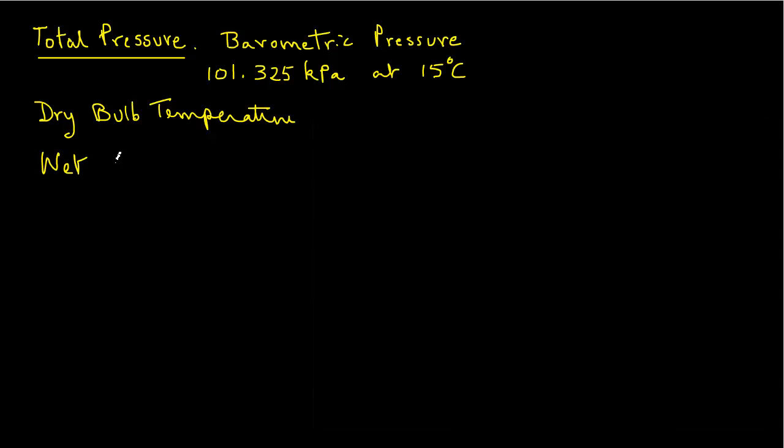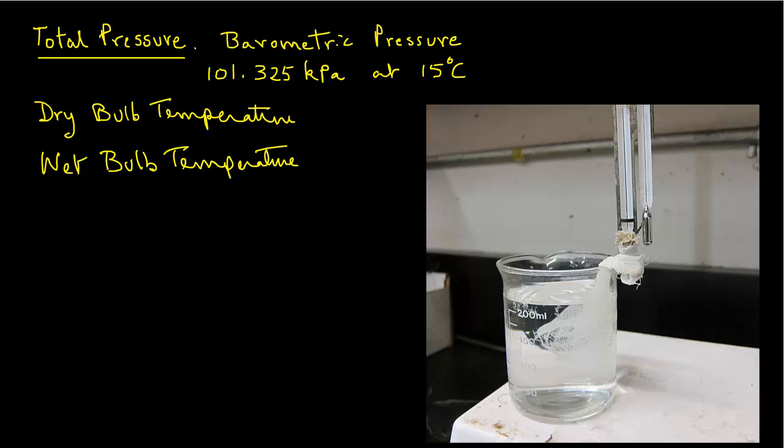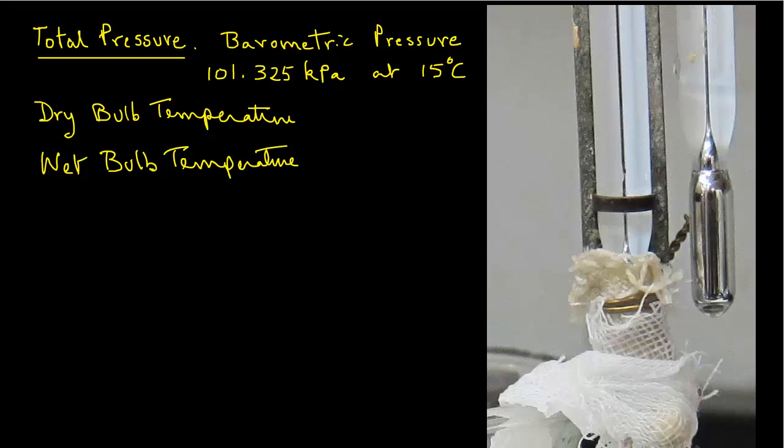Wet bulb temperature is a temperature that we measure by using a temperature sensor where the sensing element is covered with a wet sleeve. For example, the bulb of a thermometer is covered with a wet sleeve, then we record the wet bulb temperature. In addition, there must be a certain amount of airflow past the measuring sensor that has the wet sleeve on it. A minimum of 4 meters per second air velocity is required to avoid stagnant air engulfing the sensor.